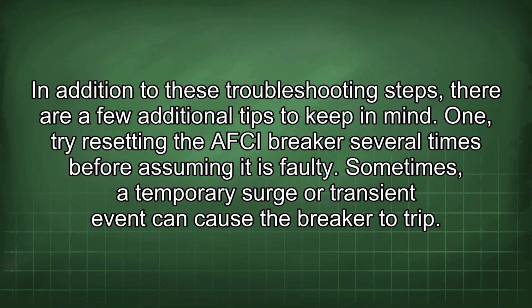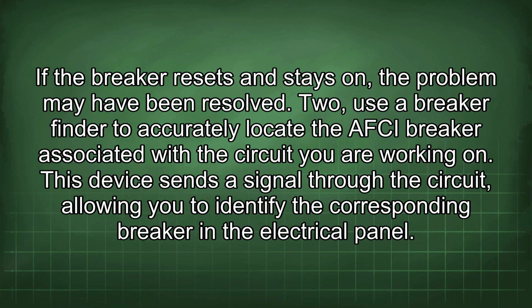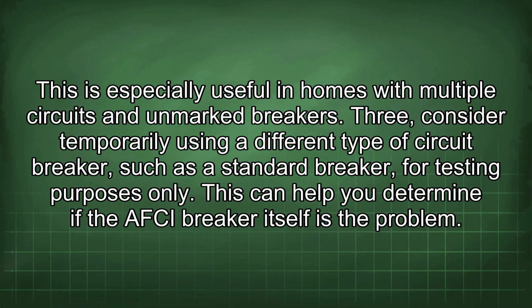In addition to these troubleshooting steps, there are a few additional tips to keep in mind. 1. Try resetting the AFCI breaker several times before assuming it is faulty. Sometimes a temporary surge or transient event can cause the breaker to trip. If the breaker resets and stays on, the problem may have been resolved. 2. Use the breaker finder to accurately locate the AFCI breaker associated with the circuit you are working on. This device sends a signal through the circuit, allowing you to identify the corresponding breaker in the electrical panel. This is especially useful in homes with multiple circuits and unmarked breakers. 3. Consider temporarily using a different type of circuit breaker, such as a standard breaker, for testing purposes only. This can help you determine if the AFCI breaker itself is the problem.